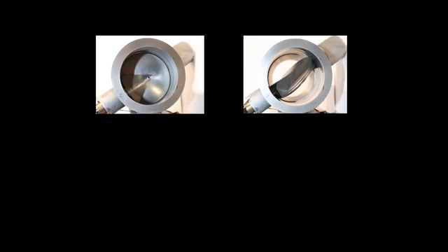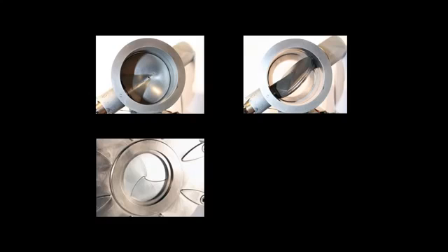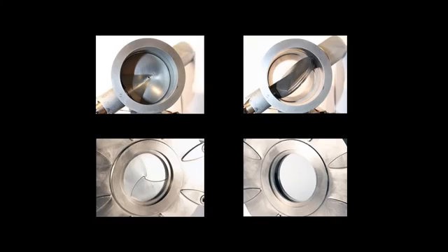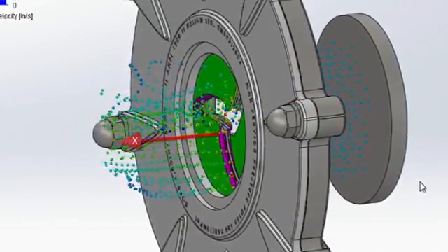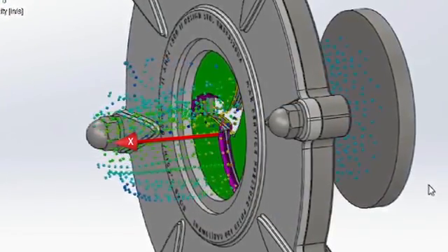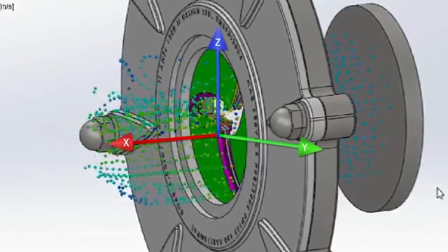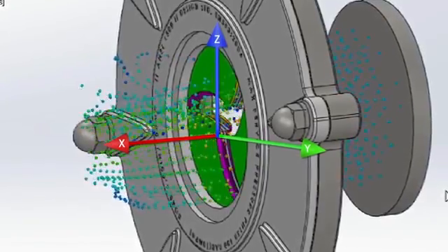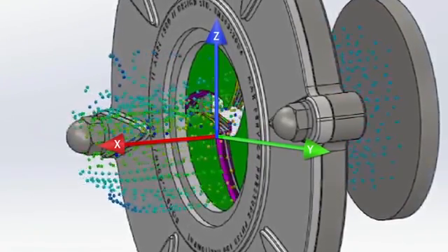It takes a huge amount of force to open a butterfly valve disc in pressurized flow, which means a large and expensive actuator needs to be used. Here the fluid flows in the x direction. You can see there is no force component in the y or z directions to affect the mechanism in opening or closing, which means the shutter valve uses less power.